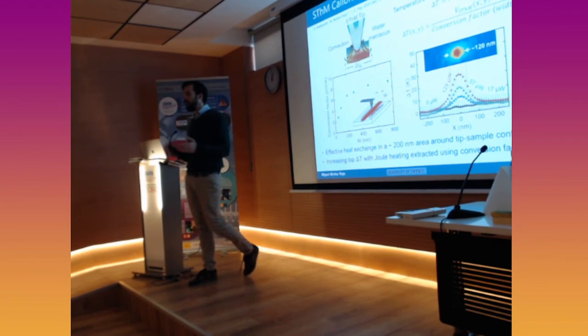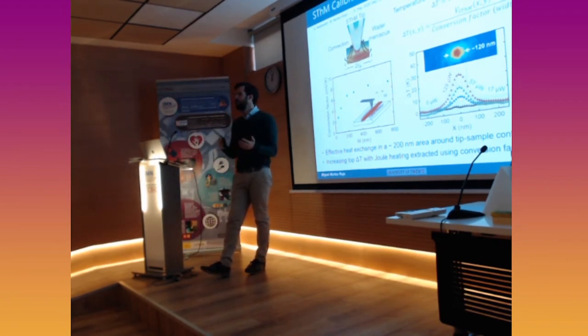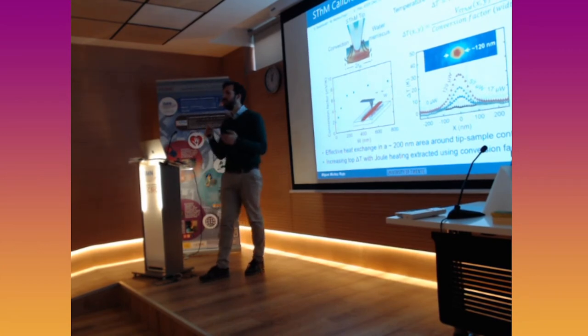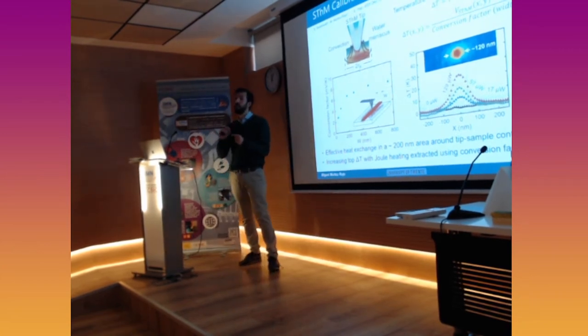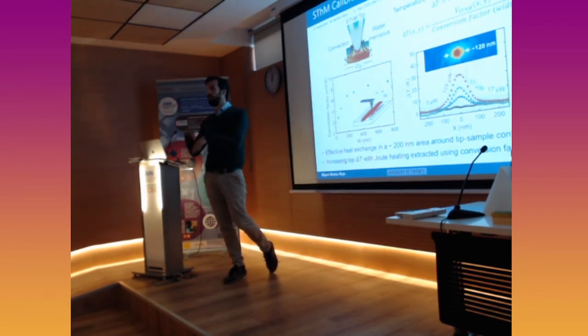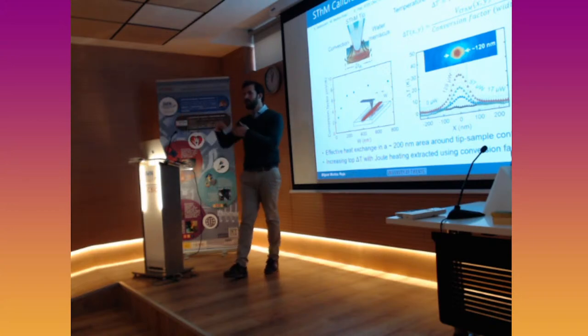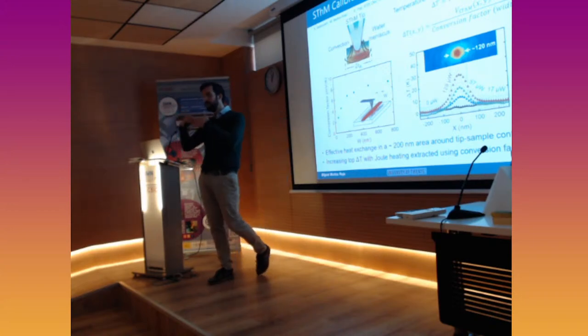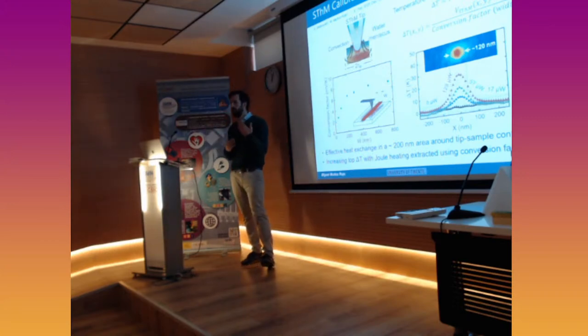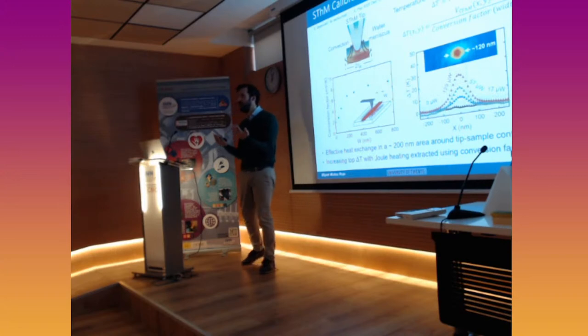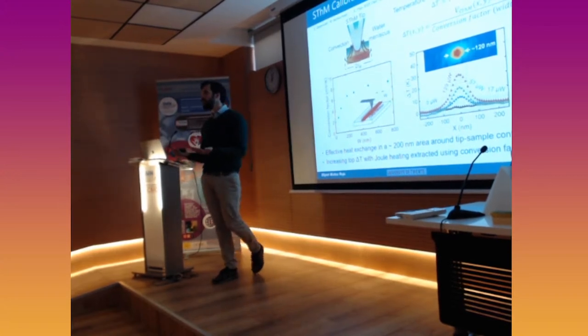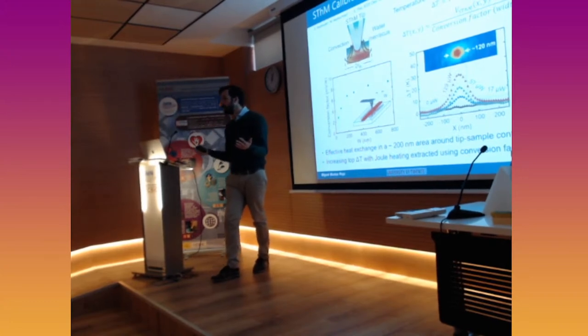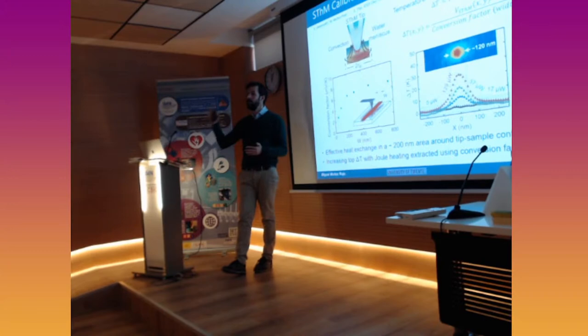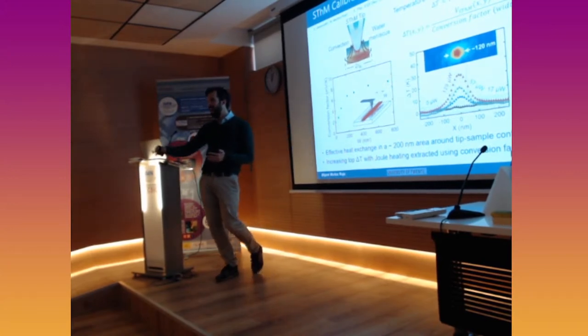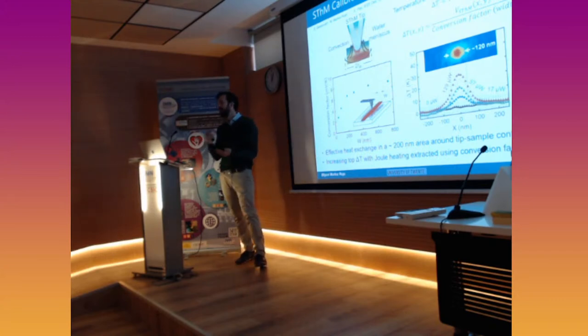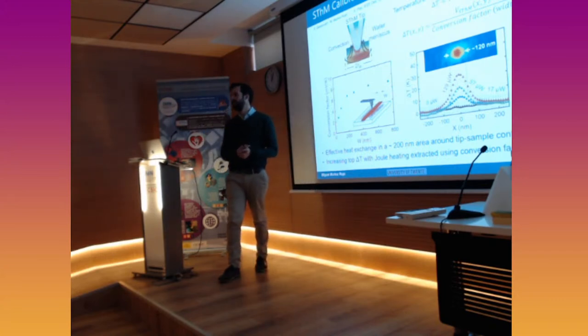There are some indications, when you have taken so many STHM measurements, that you can tell when changes have occurred in the probe. For example, you're getting a thermal map and you start seeing the background signal changing. You can do offsets and different fits, but if it changed too much, the property may have changed slightly, and then you should redo the calibration. Typically, rule of thumb, something like 100 images is more or less reliable, but it also depends on the type of devices you measure, whether they're flat or have sharp edges, and so on. It depends on many different things. It's very tedious. Okay, thank you. Thank you, Alan.